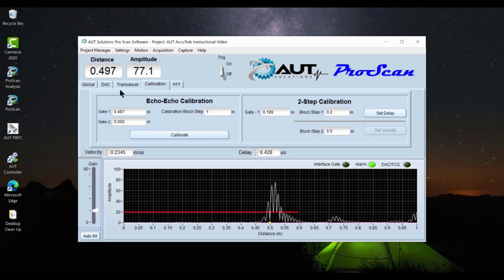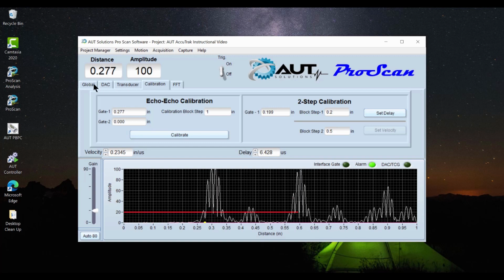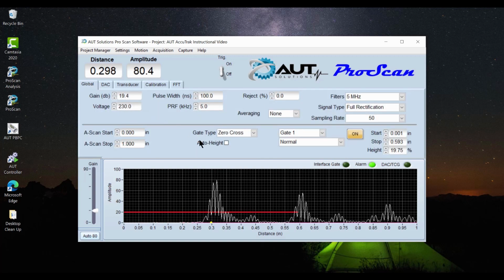So we're coming in correctly at 0.497. We'll just verify this real quick and I'll have him move to the 0.4 and the 0.3. So we are within calibration tolerance there, as we are only 1 mil off. So we are now good to go there. A couple things we're going to want to run through real quick is we will now remove the block from the test piece and we will put the probe down and make sure that our gain settings are correct.